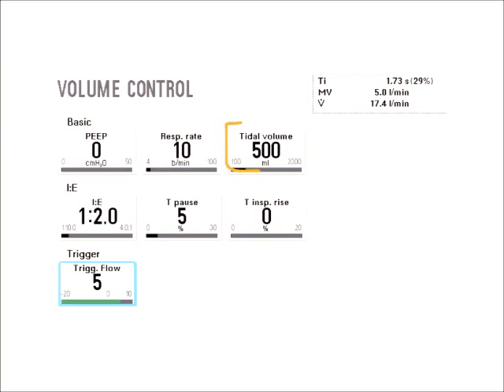Because my set tidal volume is going to be different than what actually the patient receives. So my set might be 500 cc's, but my patient might be only getting 450 cc's. Now, this is not significant in an adult patient population. However, this could be big in pediatric patients, these minute changes in tidal volume delivery.